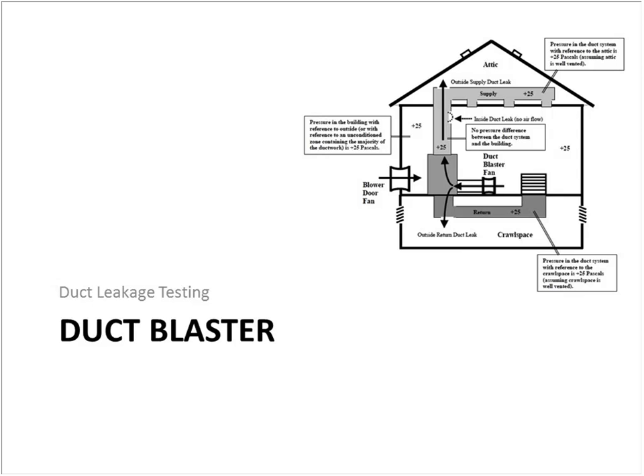And that is not a lot of leakage, especially if you've got ducts in an attic, because there can be a tremendous amount of leakage between the transition boot, the duct, and the register grill. And so it's really imperative that those areas get well sealed from the backside so that they can't leak into the attic. Flex duct doesn't leak as much in the runs as metal ducting does, but if it's not foamed and sealed properly where it's connected to metallic duct, and you're not going to do a really good job with 3 screws and mechanical tape or a zip tie, you really need to consider foaming those into place.